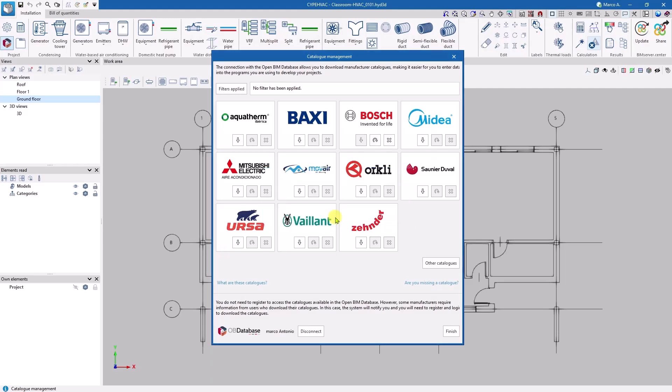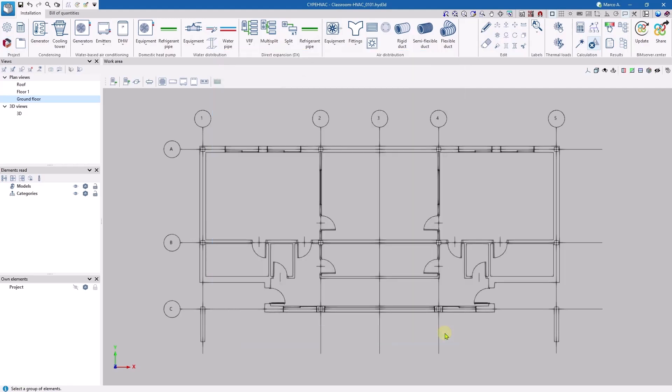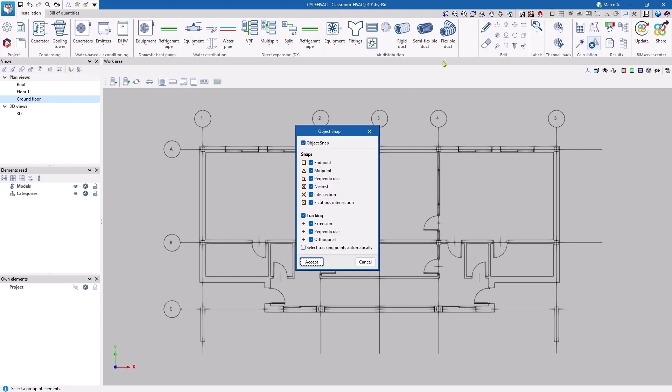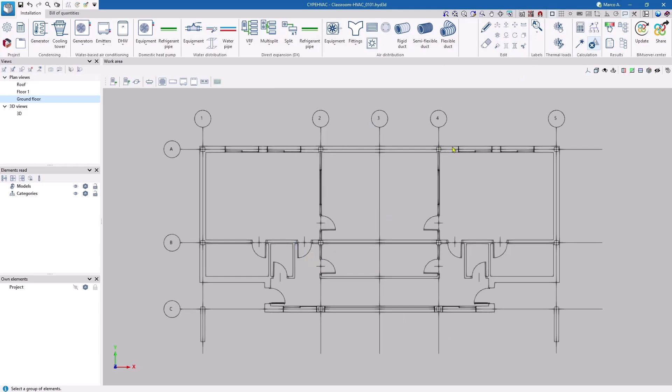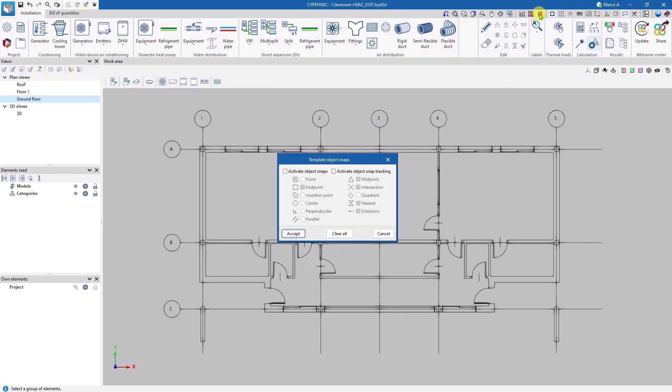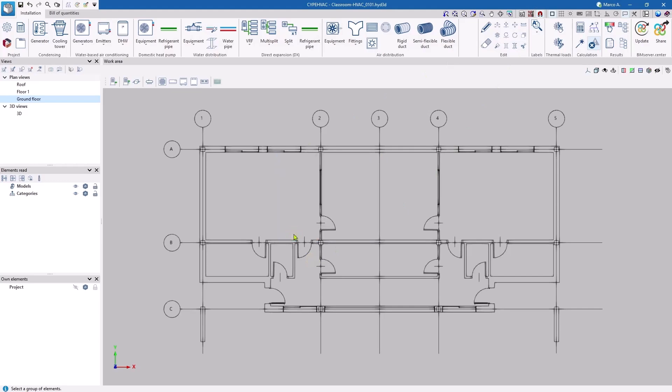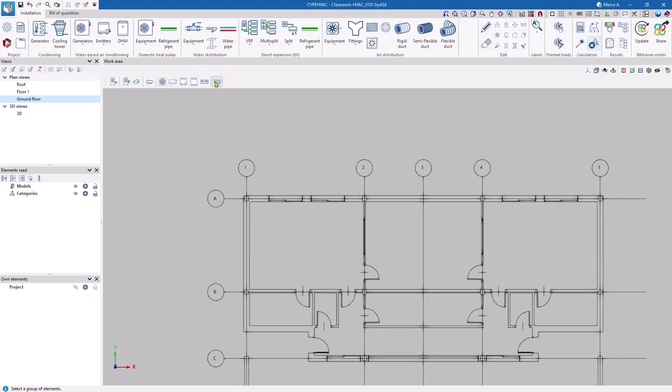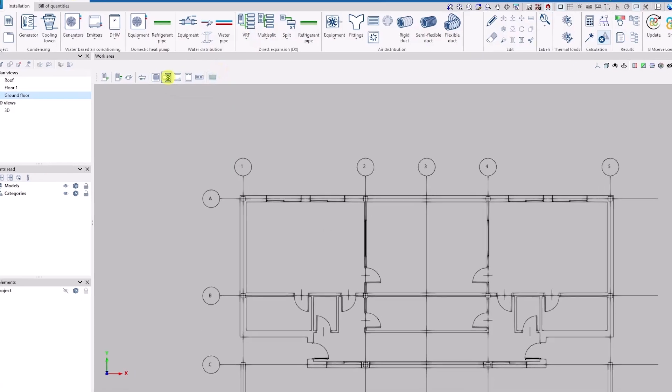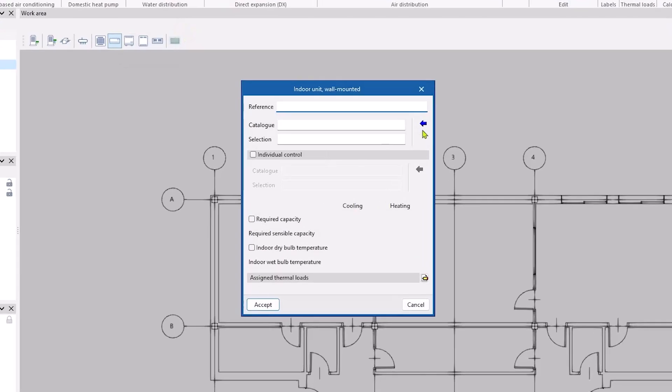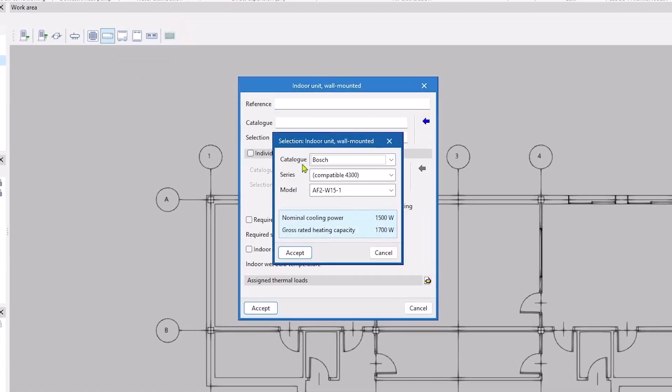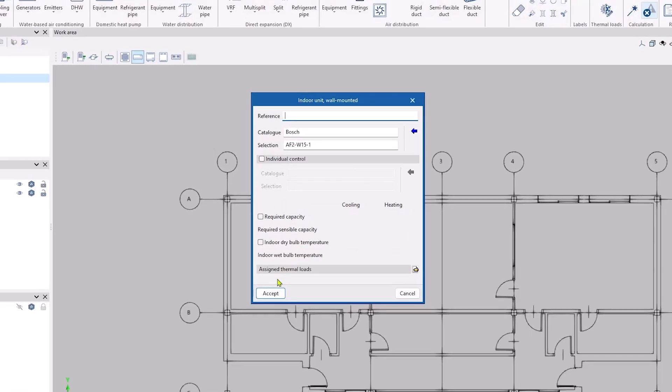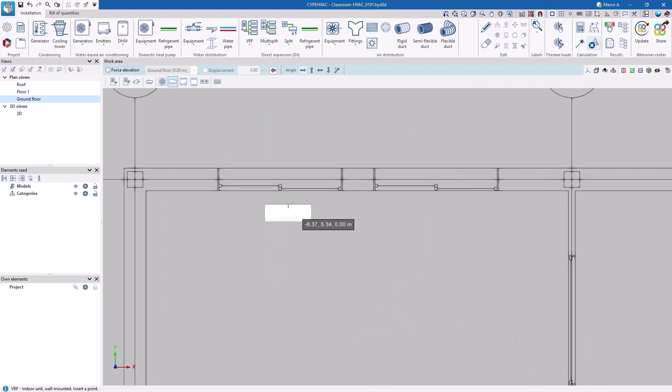First, we place some indoor units. We are going to work in 2D mode, without displacements with respect to our reference plane. The snaps of the CAD template allow us to define the precise location of each piece of equipment. Once the desired snaps have been activated, we proceed to place the equipment. We choose a wall-mounted indoor unit, and once the series has been selected, the program chooses the appropriate model according to the thermal needs.